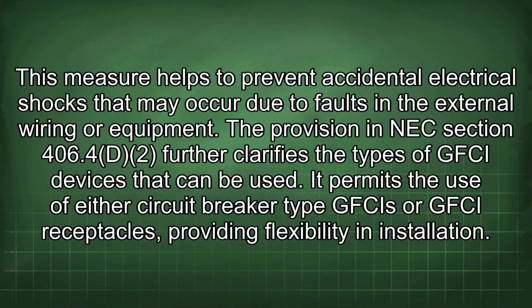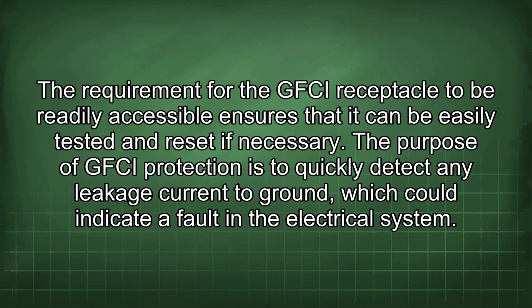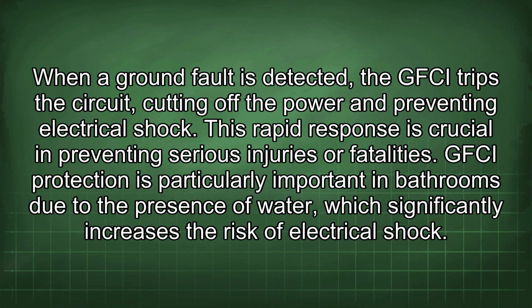The provision in NEC Section 406.4d2 further clarifies the types of GFCI devices that can be used. It permits the use of either circuit breaker type GFCIs or GFCI receptacles, providing flexibility in installation. The requirement for the GFCI receptacle to be readily accessible ensures that it can be easily tested and reset if necessary. The purpose of GFCI protection is to quickly detect any leakage current to ground, which could indicate a fault in the electrical system. When a ground fault is detected, the GFCI trips the circuit, cutting off the power and preventing electrical shock. This rapid response is crucial in preventing serious injuries or fatalities.